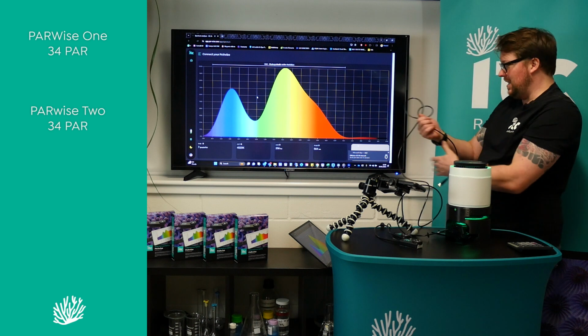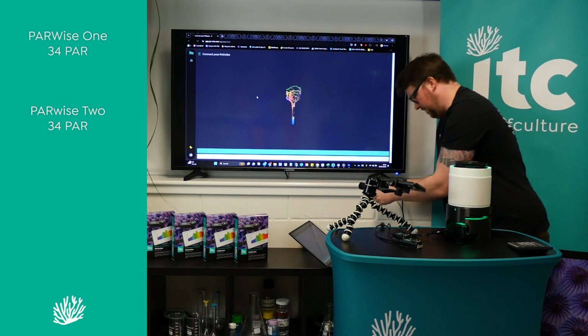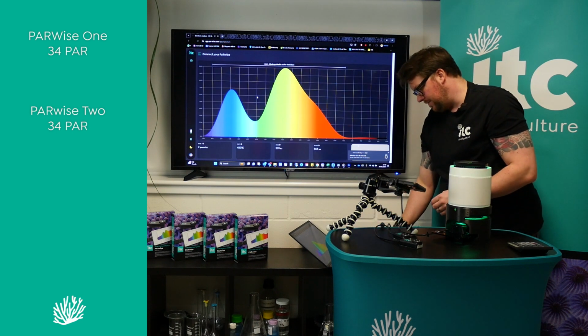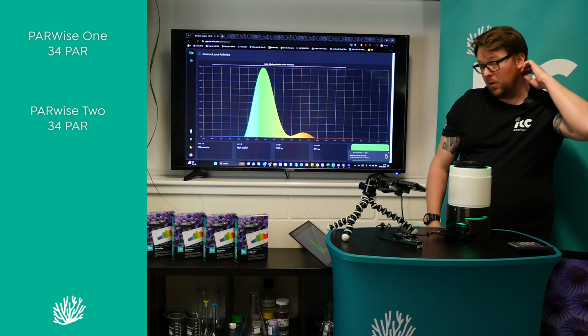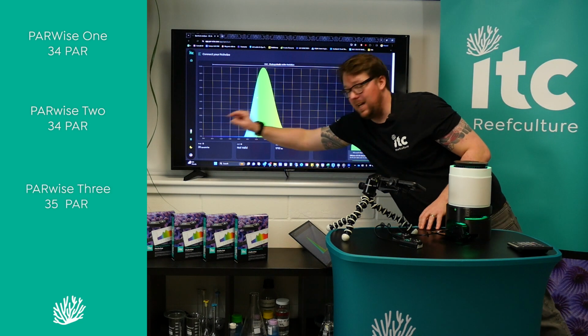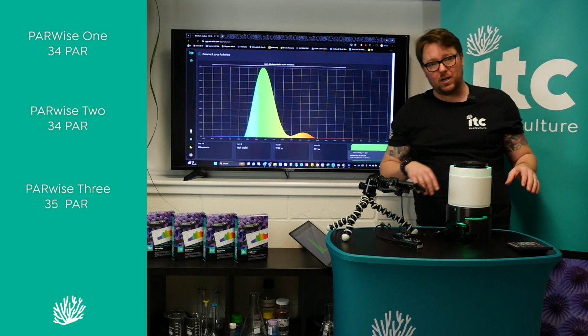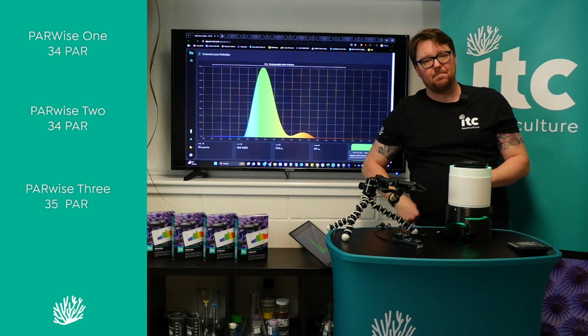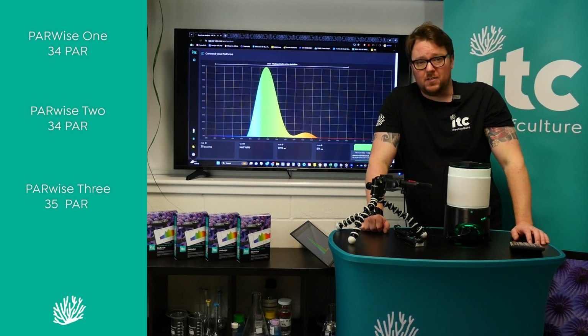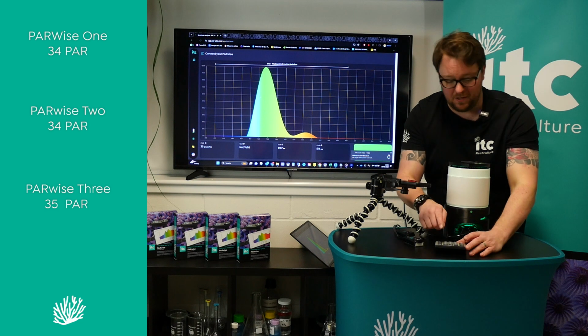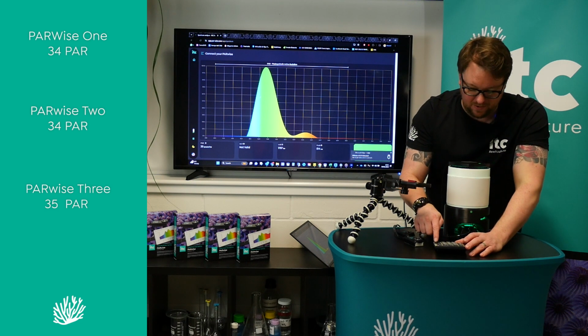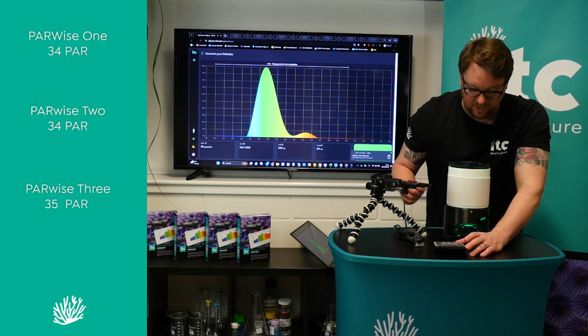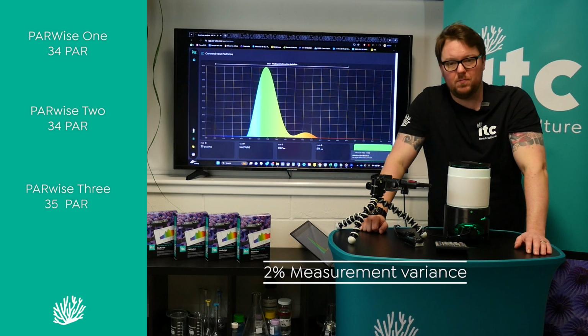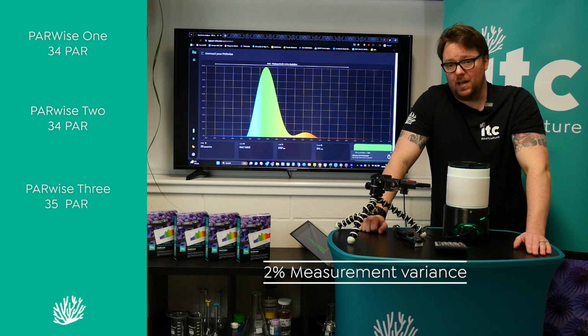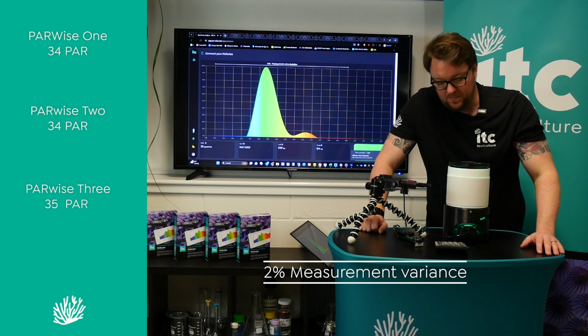Okay, sensor number 3. That's sensor number 2, still plugged in, just measuring the air for us there. There we go. Sensor number 3, 35. And it's probably worth mentioning as well, every time we've gone on here, we're in the in-air calibration mode. So just like the other ones, we were taking the correction factor off. We don't need to do that here because we're measuring in air. Okay, so that's the greens done. So we've got a difference of 34 and 35, which is obviously tiny, but 34 minus 35 divided by 34. I mean, that is a 0.02% difference. Or 2% actually, my apologies. There we go.